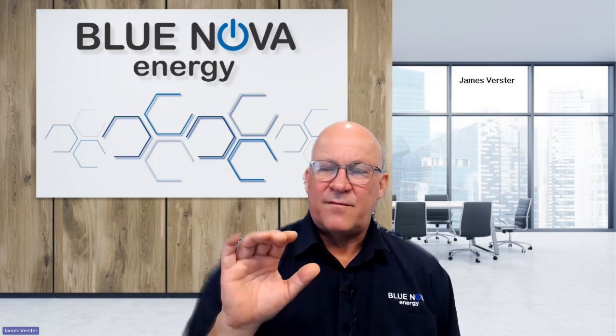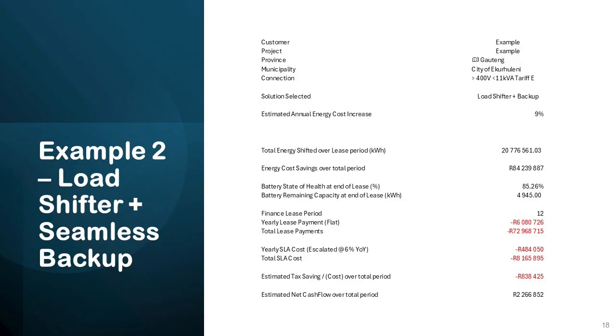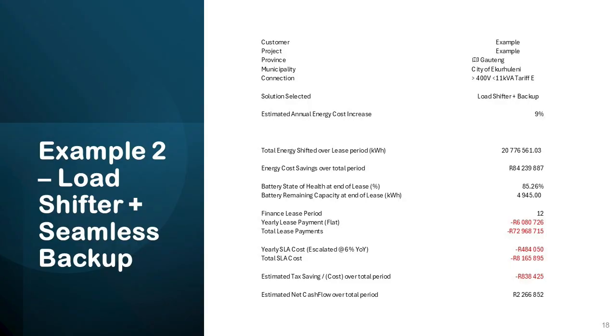Having considered that this battery has not performed any load shedding, and the value and saving of doing a 2.5-hour discharge is also excluded from this calculation. You see the battery capacity retention over that period is 85%, which allows for another 5.2% fade, having to engage with load shedding events. And there's the remaining capacity at 4.9 megawatt hours. Total lease payments at 72 million. Annual total service level cost is 8.1 million.